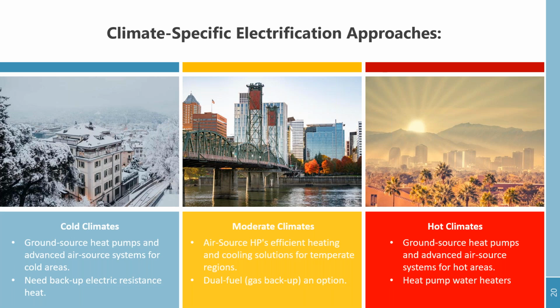It's not as beneficial to provide ground source heat pumps in moderate climates versus cold climates or even hot climates. In hot climates, ground source heat pumps can utilize stable ground temperatures for maximum efficiency in moving heat from indoors to the ground. Also, bodies of water in hot climates can be utilized if they're available near the site. Air source heat pumps can also be an efficient option in hot climates. Heat pump water heaters should be noted, and they can move heat from outdoors to water and can effectively serve high domestic hot water demands in a building. Air source heat pump water heaters can also produce usable cool air that can be harvested for space cooling.